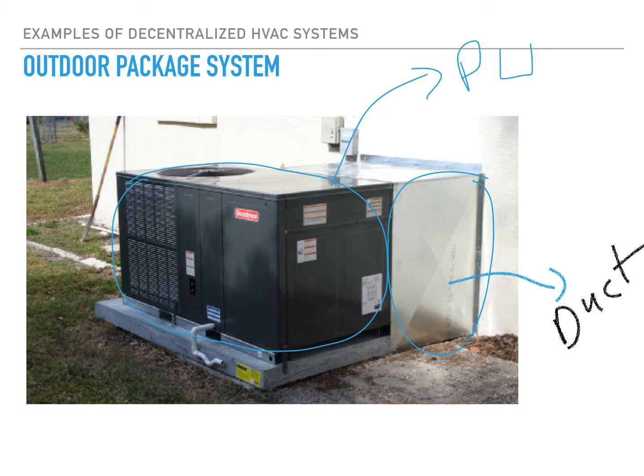The final example of a decentralized HVAC system is the outdoor package system. From the name 'package,' it means everything is packaged in one unit — one box — with all components: compressor, evaporator, condenser, and expansion valve all present in one place, shown here as the dark gray box. It has all components of the refrigeration cycle, and then cold air is simply blown towards the space through a ducting system. The bright aluminum part of the picture is the duct connected to the package unit, which distributes cold air to the required space or zone.